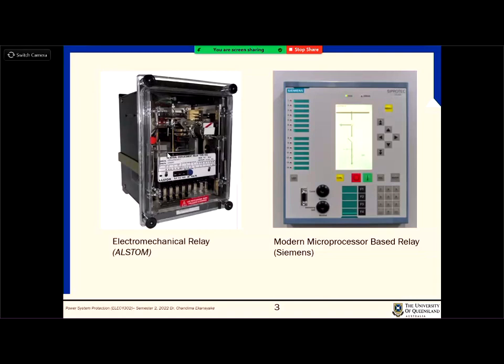So you can have a lot of mechanical arrangements to operate this, but all those things are not there in the digital. You can say, when you detect this much current, wait 0.2 seconds. You can instruct the processor, right? So those are the differences between these two. Concept wise, they are the same.